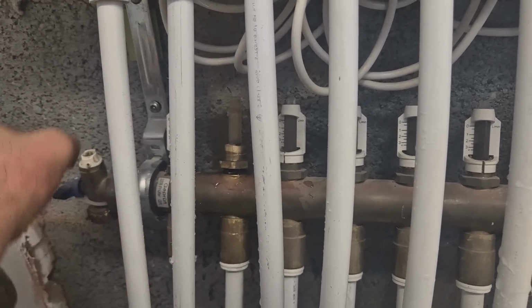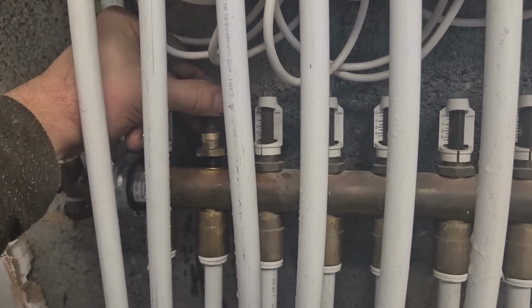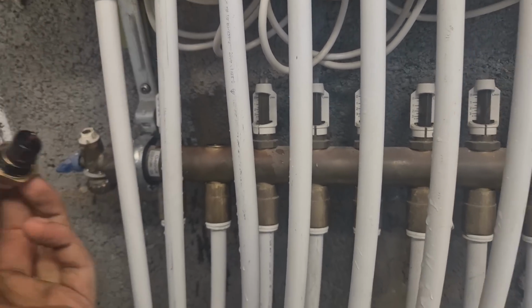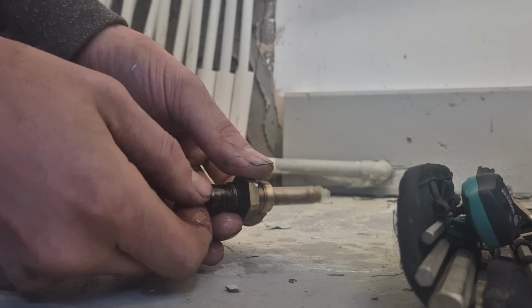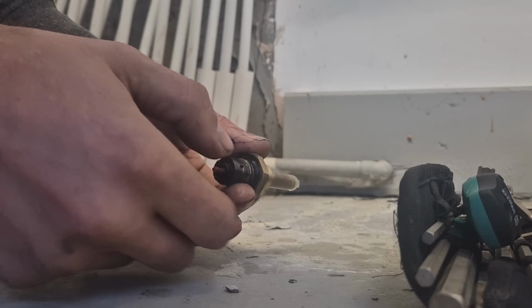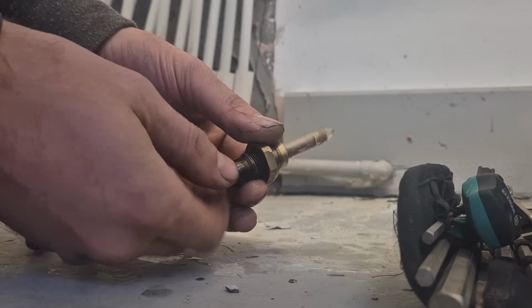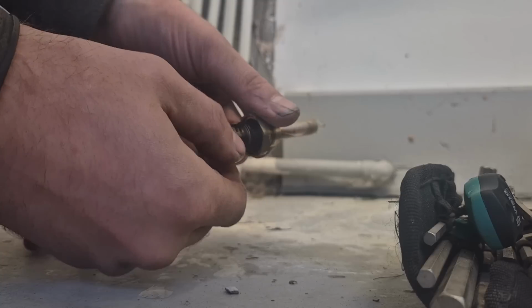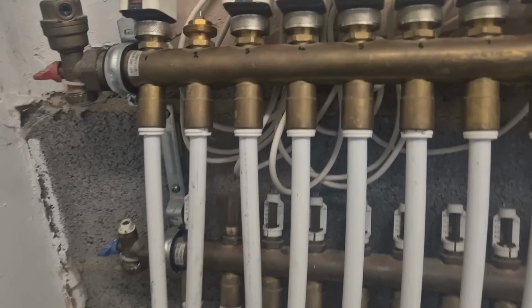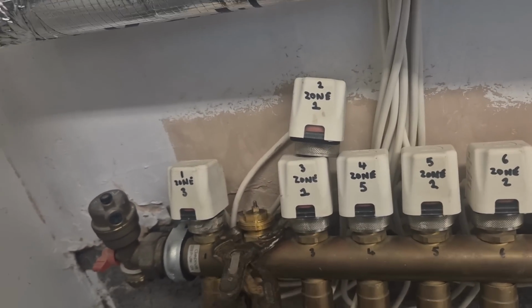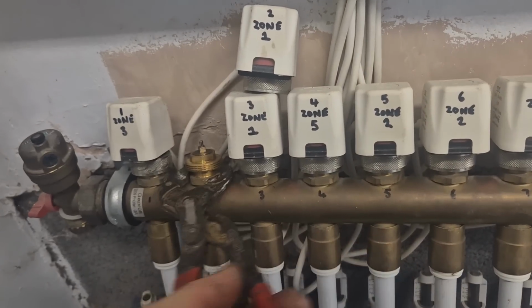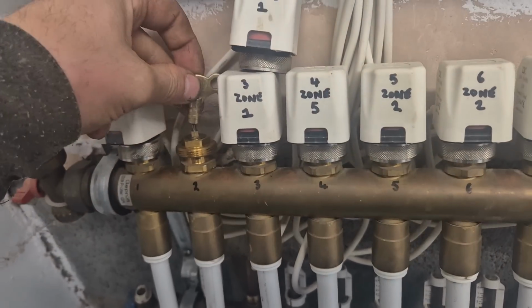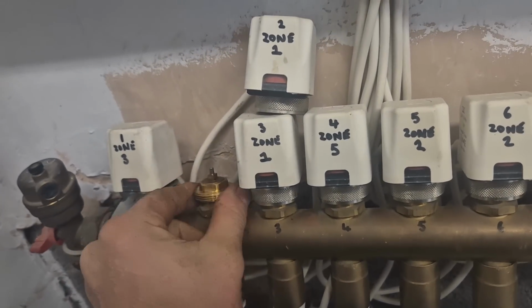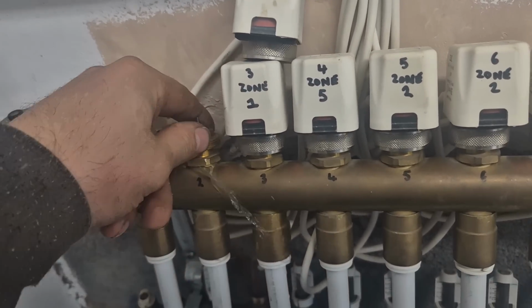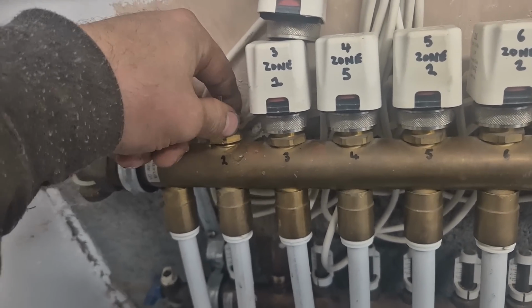In fact, it'll stop. Sometimes the pin actually drops through. You get rubbish in them and then they don't move. So we should be able to see now if that circuit's got water going through it. It's still not letting water through. The only other thing it can be is if the pin has collapsed in here. There'll be a little bit of pressure in here again because I turned it back on. To adjust these ones, you just twiddle it with your air tap, but sometimes the pin will drop all the way through and then it won't let any water in. Just let that drop. Let that water go again. We're only in a boiler room, it's not doing any damage.